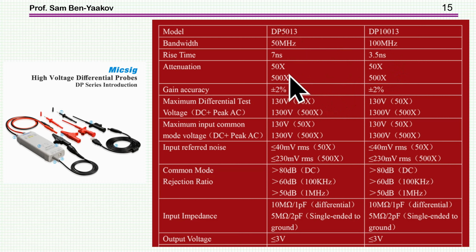Here are two models, one with 50 and one with 100 megahertz bandwidth. Both are switchable between 50 to 1 and 500 to 1, and therefore can cope with 130 volts or 1300 volts respectively, depending on the attenuation. Let's look now at the common mode rejection ratio. At DC it's 80 dB - usually with a higher end probe this number is larger. But then at 100 kilohertz it's 60, and at 1 megahertz it's only 50.